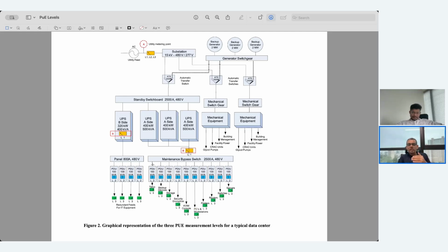To go further, where you are in an intermediate stage, where you want to do a little better, you want to have better control over PUE, you want to go a little deeper into what energy efficiency interventions can be taken up, you go into level 2, which is at the PDU level. So you are essentially measuring your IT equipment consumption at the PDU, which is in your data center. Wherever the PDUs are, that's where you are focusing on measuring the IT equipment energy.